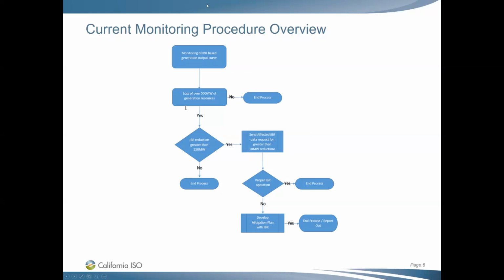We look at a 500 megawatt loss of resources, and then from there we look at whether there is 250 megawatt of cumulative IBR. If there is, we send a request to all the affected IBR that have a 10 megawatt reduction, and then we review it. If there is proper IBR operation, that's okay. If not, then we'll have to develop a mitigation plan with the IBR. That's basically the bigger picture of the flowchart of what we are doing in the monitoring.